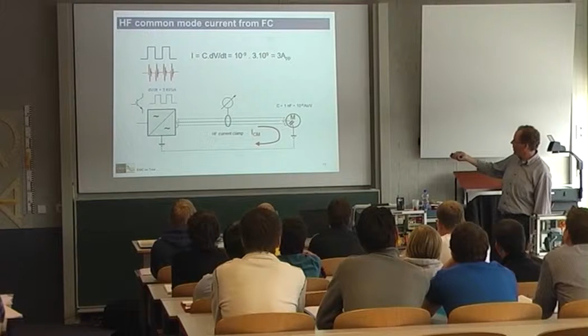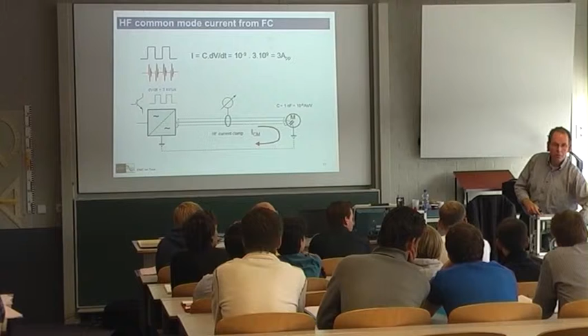So what's the idea of using the screened cable? Because what I'm doing now, I will first show you the effect without the screening effect. So I've got the cable braiding, the shield terminated here with a gland. So it is a metallic connection between the shield and the motor casing. But at this end here, it's hanging loose, so there's no shield connection. And then in the second stage I will connect the screen. But any idea what happens if we connect the screen at both ends? You get another connection, another loop. So you get a second loop, yeah. And Fritz explained about Lenz's law, and of course it's more energy to go this way, far away from the cable, so through the neighbor's circuitry. It's easier to go back on the screen, of course.